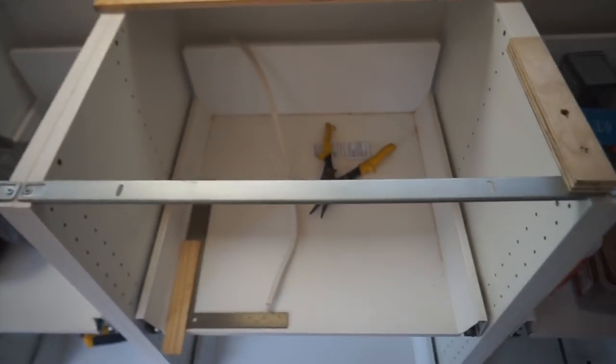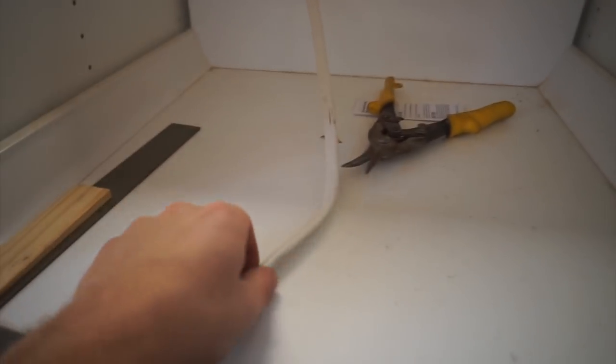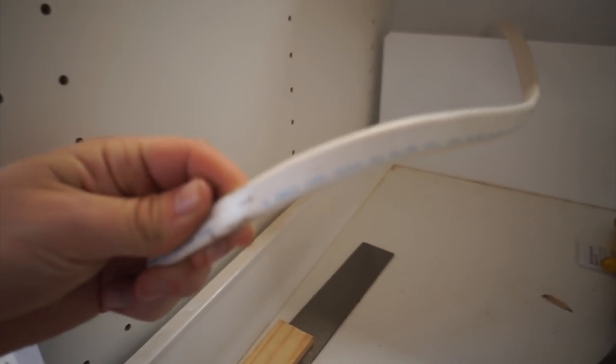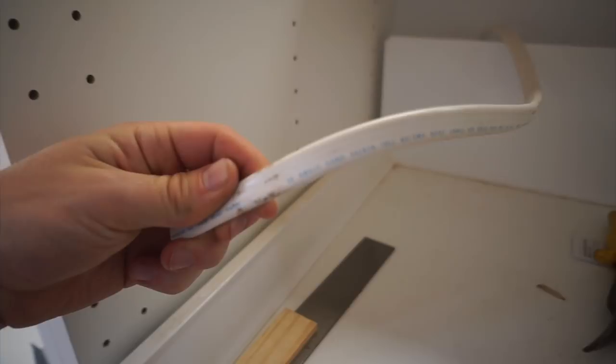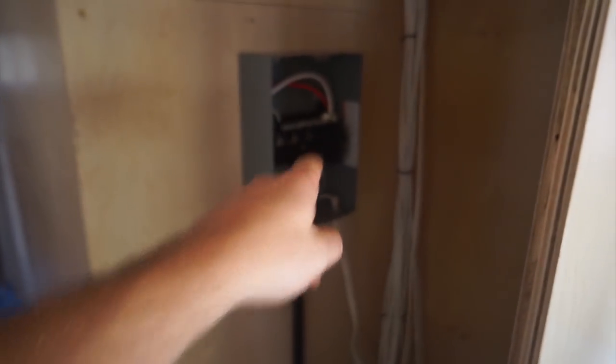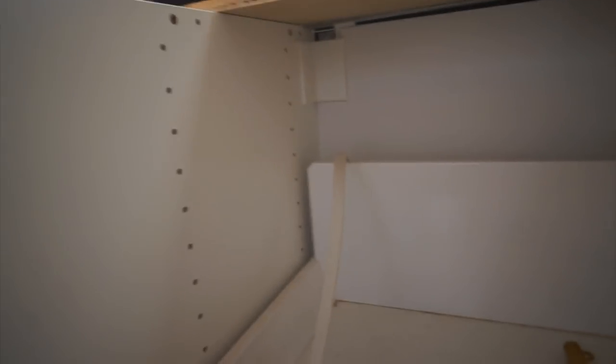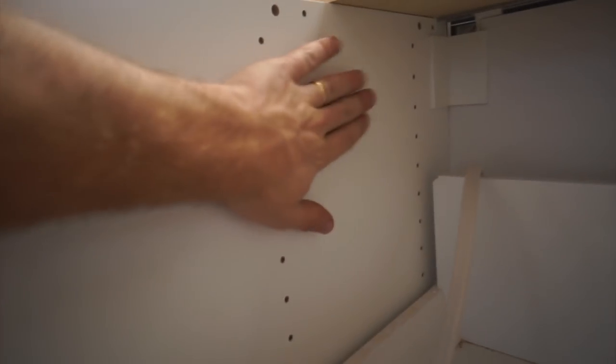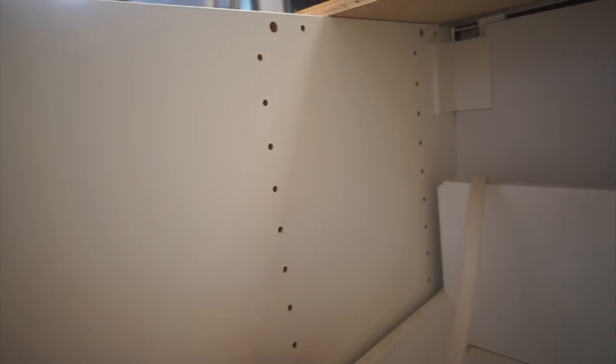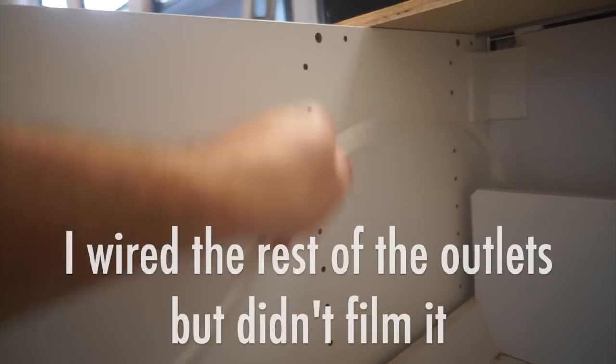Sweet! All right, so next up I have the induction cooktop. The induction cooktop wants a 20 amp outlet, which means I need a 12 gauge wire. Good news, this is 12 gauge because I planned ahead. And then I need a 20 amp breaker in that box. Oh yeah, the cooktop gets plugged into an outlet. So I'm going to be mounting an outlet right here and putting this wire in there.